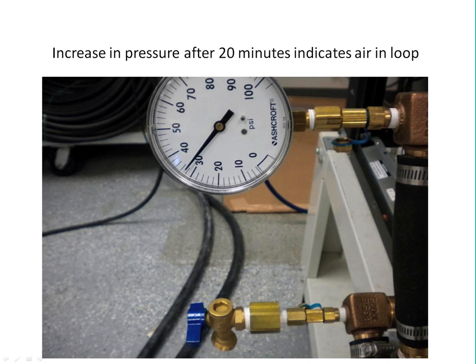If that needle starts to climb, that typically means you have air still in the system, because remember, air and gases compress, liquids do not. So that is another simple test to determine if you have bound air or captive air in that system. And if you do, you're going to have pump problems, performance problems. It'll be noisy. You could eat a pump, maybe two. But also you could have a loop out there that is airbound, which means it is not contributing heating or cooling. So it's time to bring out the appropriate flush cart and follow those flushing procedures.